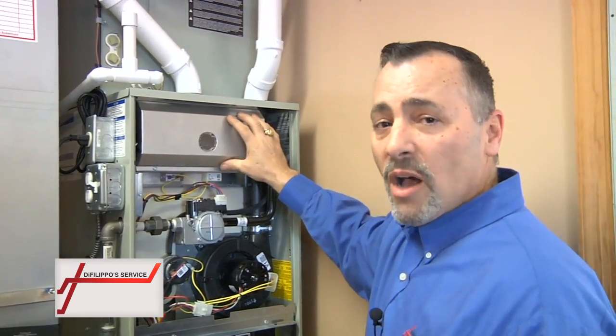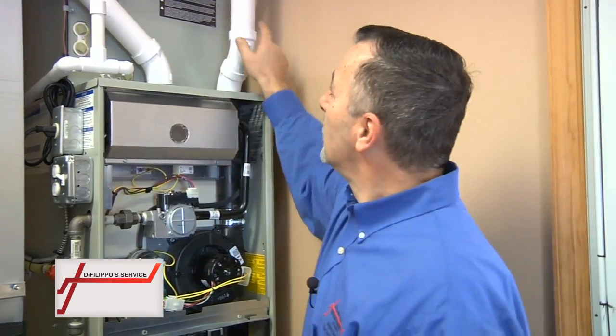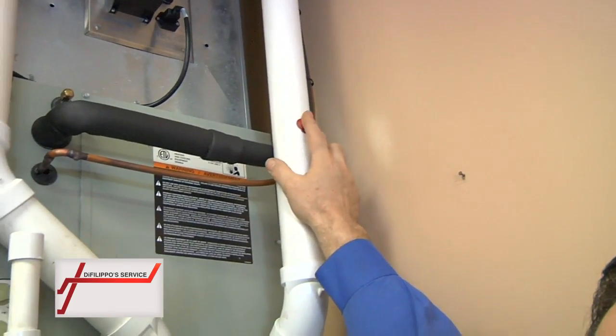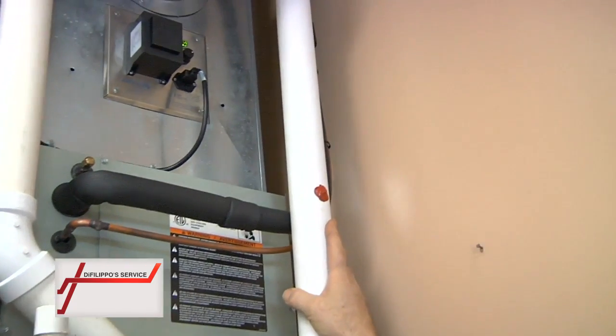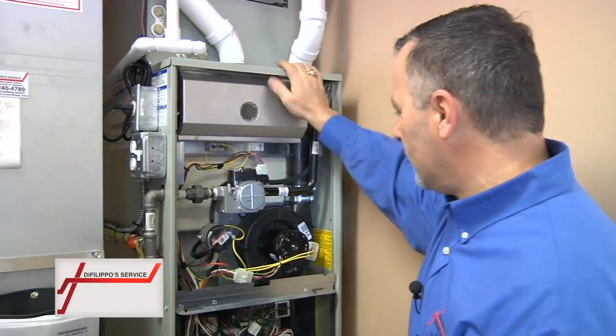The way we also confirm that your furnace is burning at top efficiency is we do a carbon monoxide efficiency test. You ever see a little piece of red on your flue pipe, even with the metal? That's where we put our CO analyzer in, and it tells us exactly how this thing is doing. We bring it to the proper firing rate, so for all those dollars you put in, you get the most amount of heat out of it.